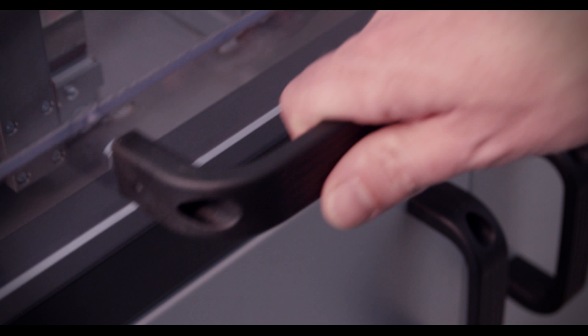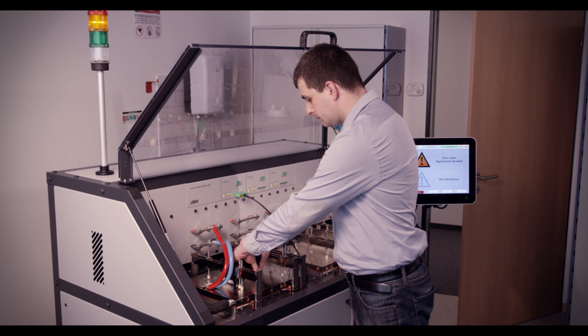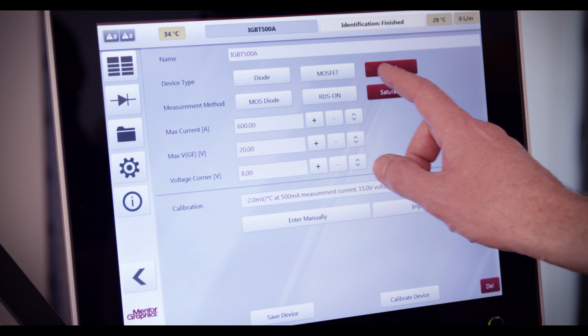The PowerTester 1500A is a standardised and tested system, capable of running for long periods of time, enabling designers to characterise the thermal performance of components at high power by testing them at the very limits of their operation.